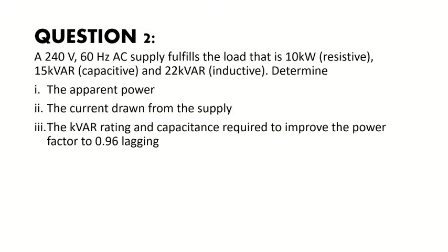Determine the apparent power, the current drawn from the supply, and the kVAR rating and capacitance required to improve the power factor to 0.96 lagging.